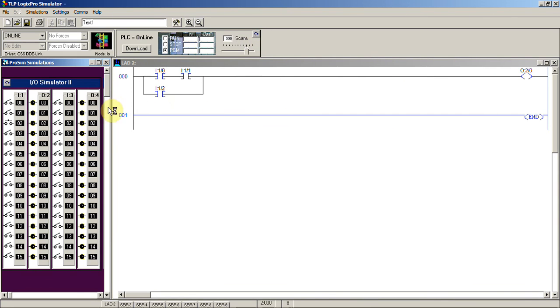After this we'll just download this program to the PLC, and then we'll keep the PLC in run mode, and now we will check how the output behaves. So now this temperature switch will be closed, and now you can see that particular part is highlighted. Then the one more switch, the pressure switch, also closes when it reaches its value, and now this is also highlighted, and there is logical continuity to the output. So the output is also highlighted, meaning the output is energized. As you can see here in output terminal 2, this LED, or the indicator lamp, is turned on.